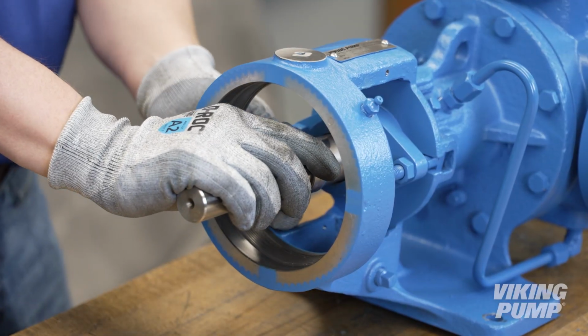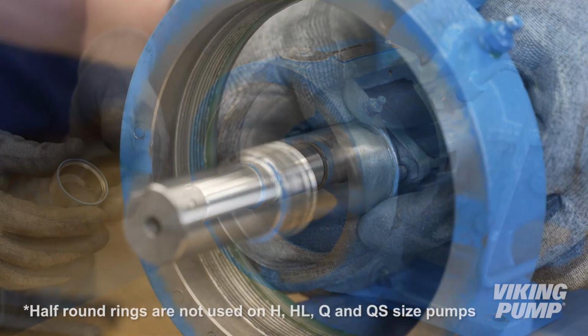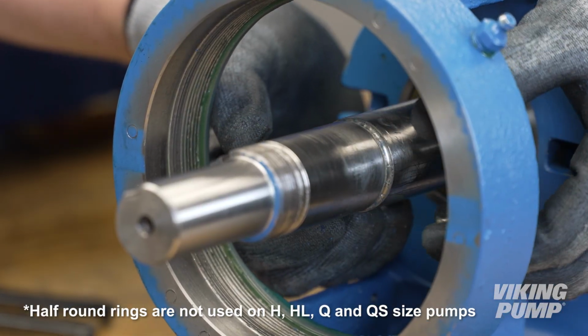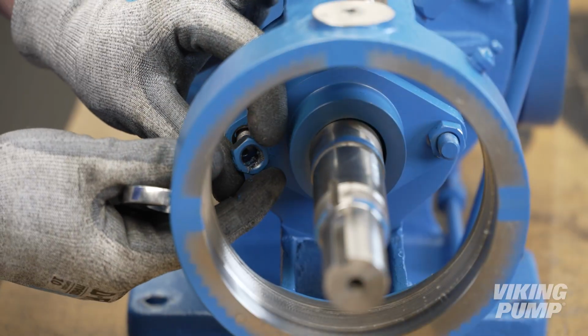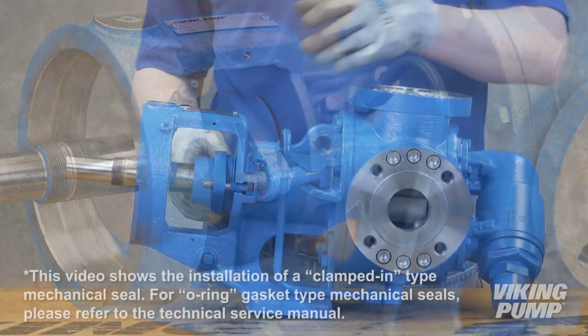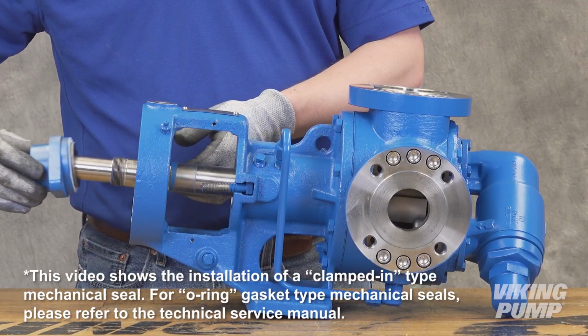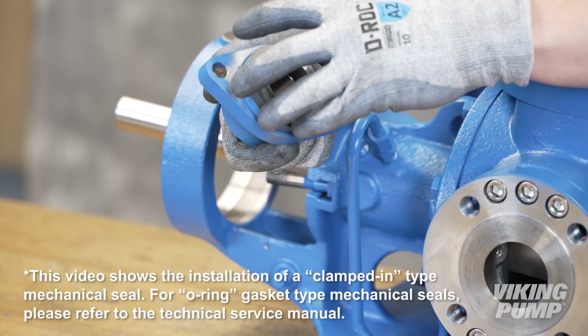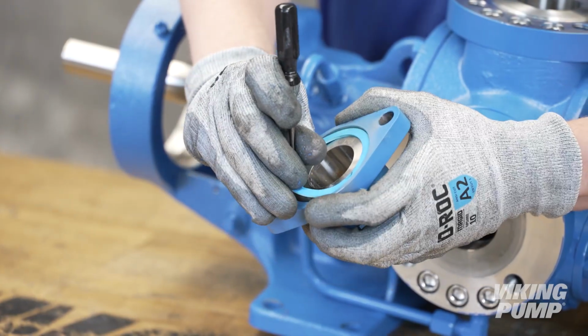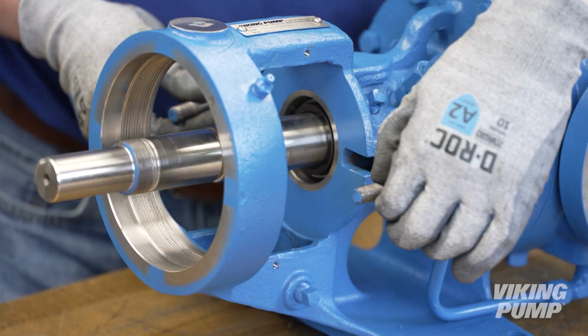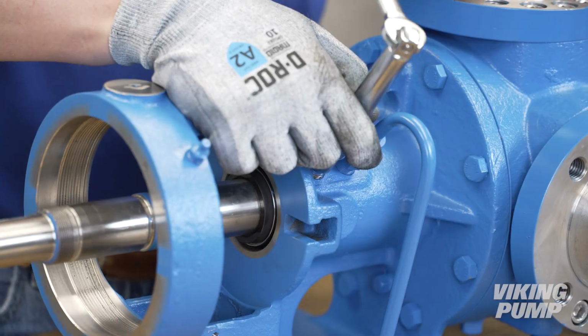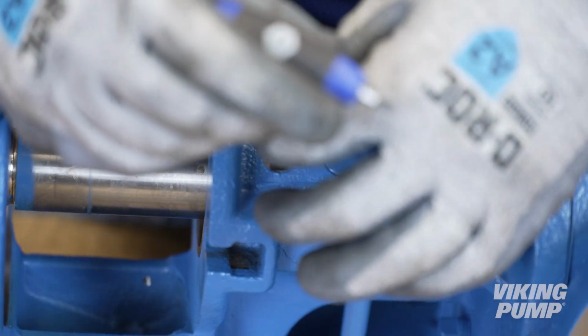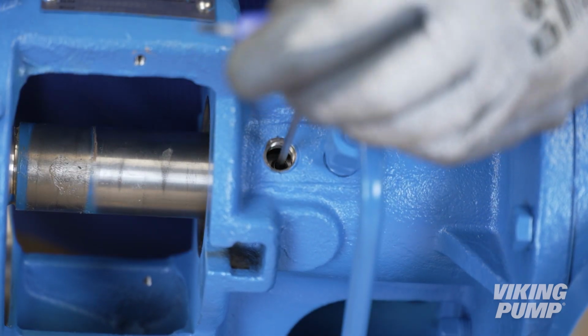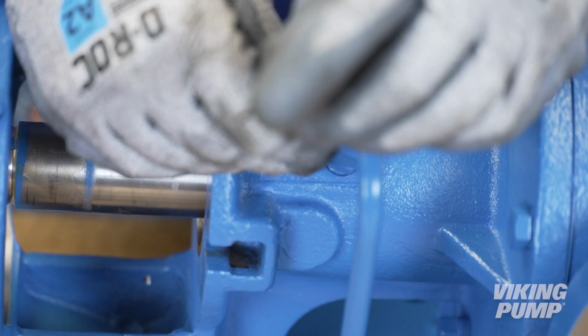Remove the bearing spacer collar. The collar may have come out with the bearing housing. Remove the half-round rings. Loosen and remove the seal holder lock nuts. Remove the seal holder, seal seat, and seal gasket. Remove the T-bolts. Remove the seal access hole plug to reveal the seal set screws. Loosen each of the seal rotary member set screws. Carefully shift the rotary member down the pump shaft so it can be removed.